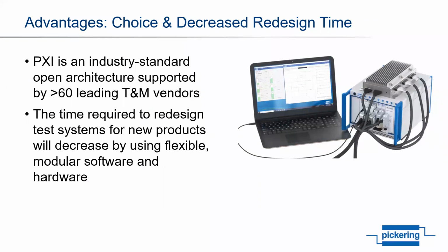PXI, which stands for PCI extension for instrumentation, is an industry-standard open architecture which is maintained by the PXI Systems Alliance and supported by over 60 of the leading test and measurement vendors. Having so many vendors support the architecture means that a system designer can pick and choose building blocks from multiple vendors depending upon their requirements, rather than being tied into a single vendor.